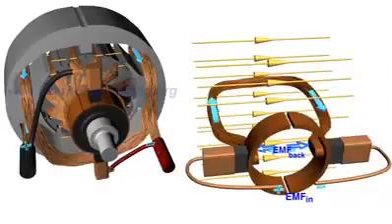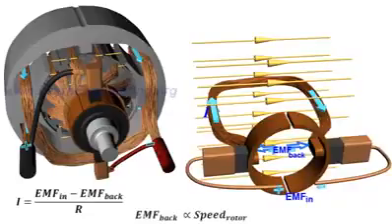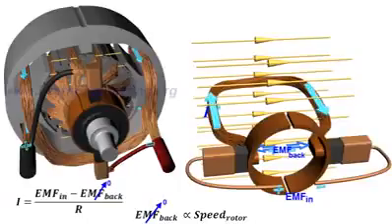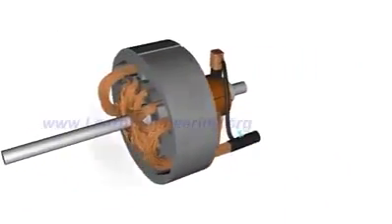The back EMF reduces armature current by a large amount. Back EMF is proportional to the speed of the rotor. At the starting of the motor, back EMF is too low. Thus, the armature current becomes too high, leading to the burnout of the rotor. Thus, a proper starting mechanism that controls the applied input voltage is necessary in large DC motors.